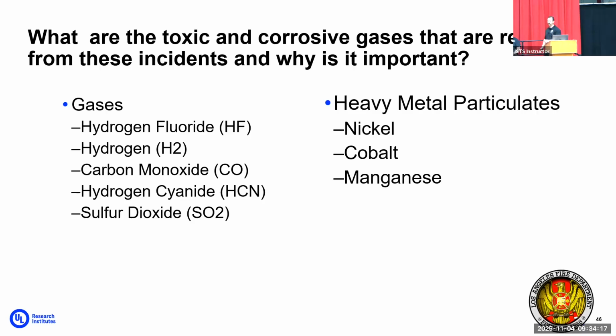Hydrogen is another byproduct of the electrolyte in the battery. The electrolyte produces a lot of the flammability and the explosive gases that come into that environment. We're going to show some examples down the road, but hydrogen, if you don't know, is a very explosive gas. You don't need much - 4% to 75% is actually the explosive range of hydrogen in an environment. When we have that in a confined, enclosed environment, it leads to a possible explosion, and we're going to talk about that in the next few slides.